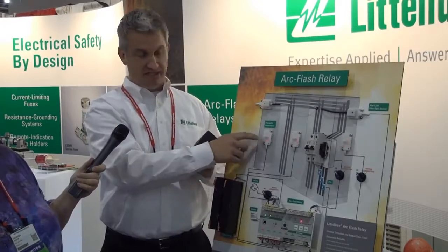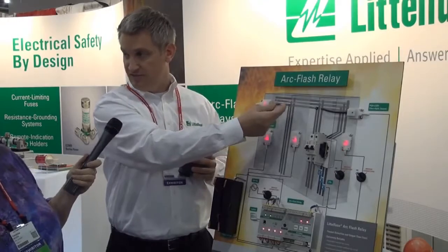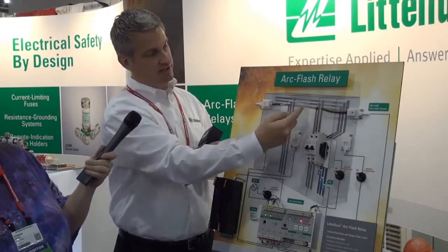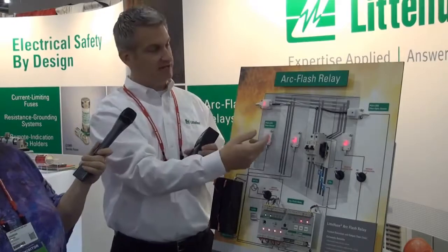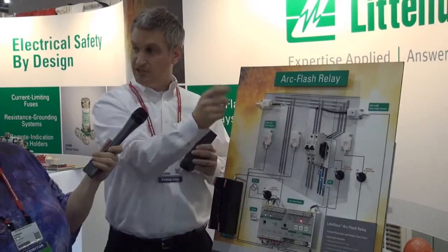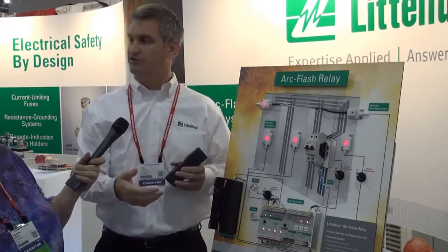If you run into a motor control center where the buckets are very small, and you would have to have one of these for each bucket, may not be practical, you can take this fiber optic here, and this is actually 25 feet in length. It actually goes continuous into here, but for demonstration purposes, it's bundled in the back there. You can take 25 feet of this fiber, and you can string it along all the buckets. And so you get greater coverage this way. The only downfall of that is you don't know exactly which bucket had the arc flash, because anywhere along this fiber, that's where it sees the arc flash, and it would then channel that signal back into the relay here. So it depends. If you have a bunch of tight, small compartments, you would probably use a fiber optic to be strung through them. If you have a big open compartment, you'd use a point sensor there.